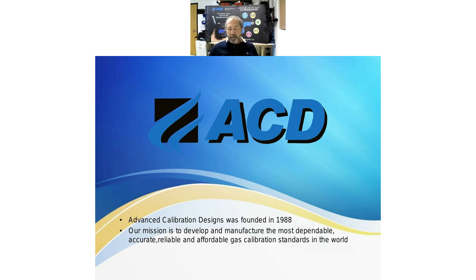So we kind of stayed in the toxic or slightly explosive gas area. And what we've made are handheld, battery operated calibrators for gas detection equipment that are primary standards, and these things are used to calibrate sensors. We don't have calibrators for every single kind of gas, but the ones we have are adjustable and, as it says here, dependable calibration gas standards.